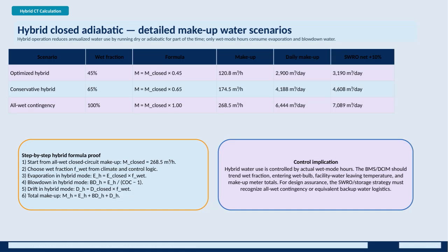Here we are looking at the hybrid closed adiabatic cooling tower calculation, focusing on detailed makeup water scenarios. The key advantage of hybrid operation is that it reduces annual water use by operating dry or in adiabatic mode for part of the time. Only when the system runs in wet mode do we consume evaporation and blowdown water.